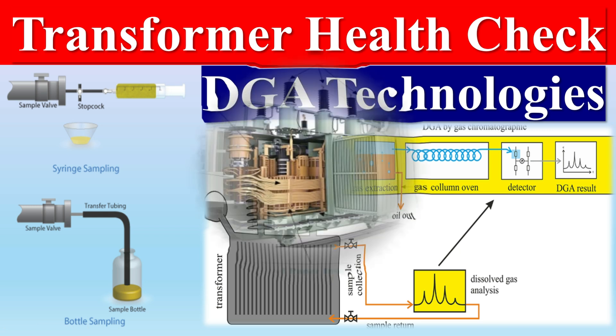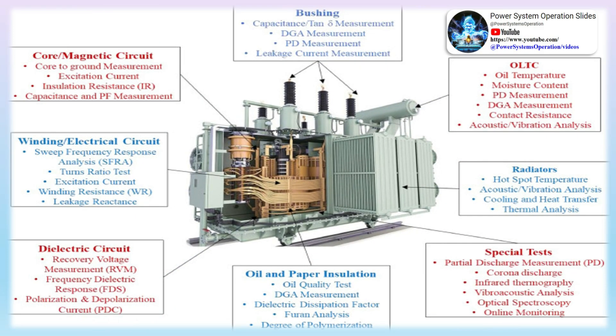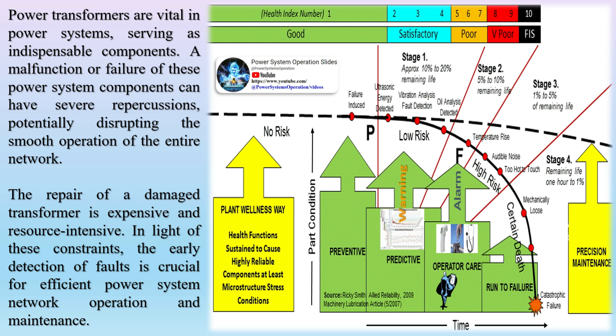At a time when the optimal utilization of resources is becoming ever more important, the condition monitoring of electrical equipment is also becoming increasingly essential. The Dissolved Gas Analysis, an internationally accepted method for the condition assessment of transformers, plays a key role in this respect. By continuously monitoring the key gases in a transformer, incipient faults can be detected at an early stage and suitable maintenance measures can be initiated. This ability to plan maintenance measures may provide the key to cutting costs and increasing the overall system reliability.